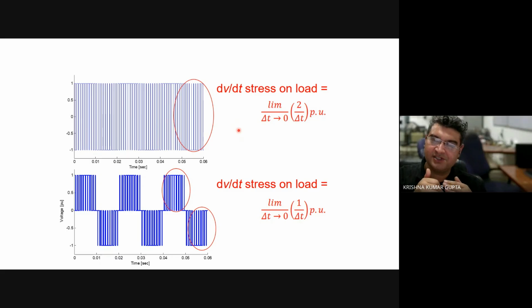So basically that can be modeled like a capacitor. All the current that we want to flow through that stator winding is only through the conductor. We don't want the current to flow through the insulation part, because if current flows through the insulation, it will damage its insulating property, and over a period of time there will be a lot of wear and tear on the insulation part, and a time will come when there will be a direct short circuit in the windings of the motor, the stator winding of the motor.